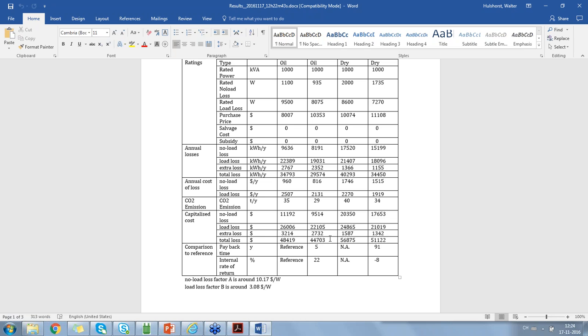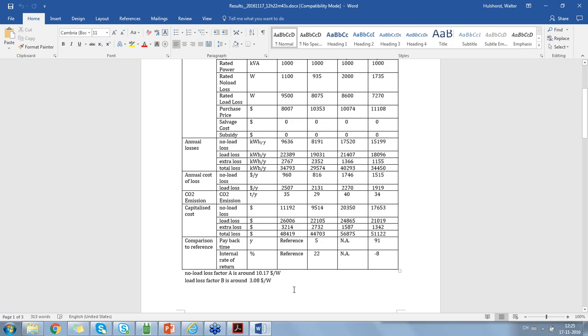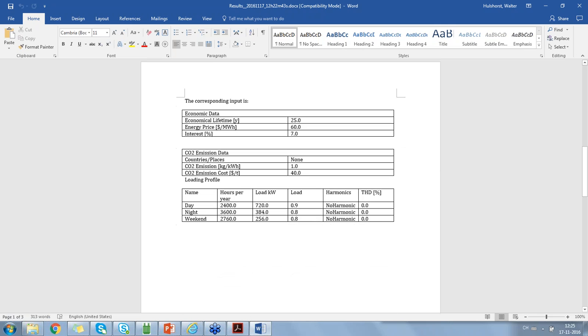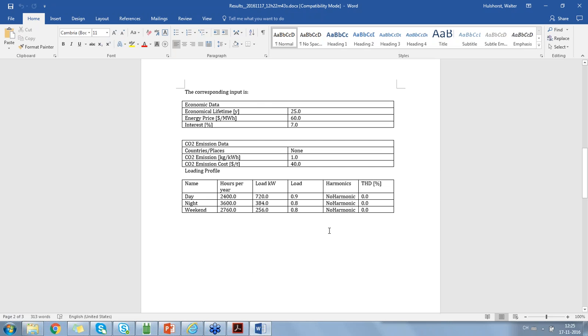It's calculating the no load losses, the amount of money, and also the load losses and the extra losses in total which you have. Then it's giving you a kind of payback period referred to the reference. In this case, transformer number 1 is the reference. And I already told you, in case you don't know the A and the B, which are the evaluation for the load loss and the no load loss, this tool will calculate them for you as well. So in this case, it's about $10 per watt for the no load losses, and for the load loss it's about $3 per watt.